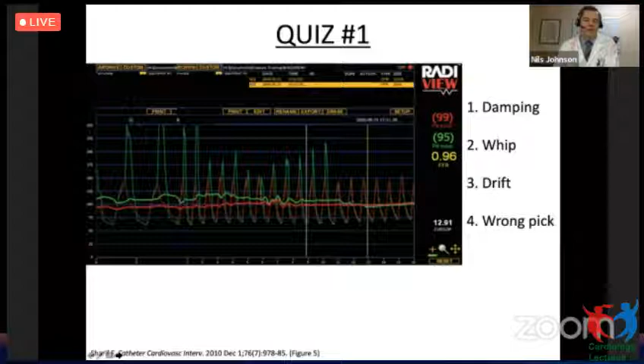And I've given several choices here over to the side. You don't need to vote, but just maybe in your own mind, think about what's causing what we see on the screen and what you would do to make it better if you had to troubleshoot this in the cath lab in real time. And this is an example of whip. You'll notice here during the very peak part of systole that the pressure in the coronary artery, the green pressure, rises dramatically above the red aortic pressure. You can see here that the aortic pressures may be at 140 millimeters of mercury, but the pressure in the coronary wire spikes up to over 200, almost 250 millimeters of mercury. And this happens with every single heartbeat right at the peak of systole.